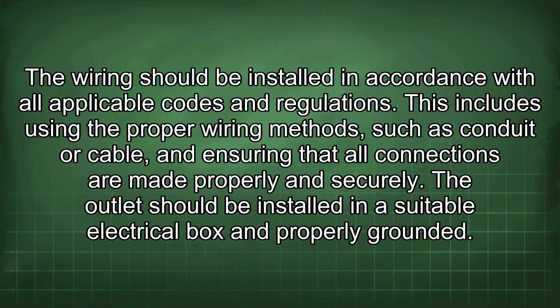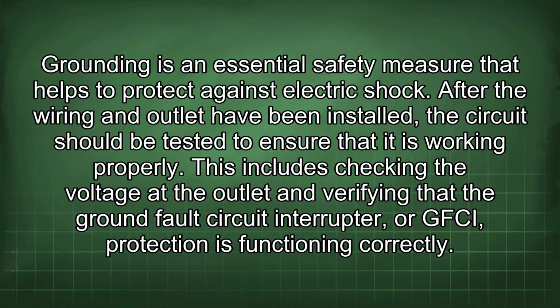The wiring should be installed in accordance with all applicable codes and regulations. This includes using the proper wiring methods, such as conduit or cable, and ensuring that all connections are made properly and securely. The outlet should be installed in a suitable electrical box and properly grounded. Grounding is an essential safety measure that helps to protect against electric shock. After the wiring and outlet have been installed, the circuit should be tested to ensure that it is working properly. This includes checking the voltage at the outlet and verifying that the ground fault circuit interrupter, or GFCI, protection is functioning correctly.